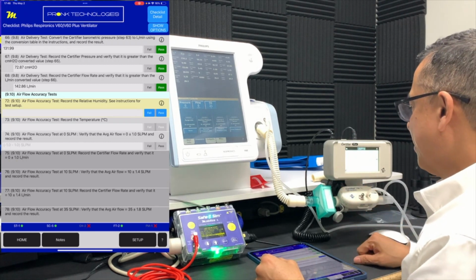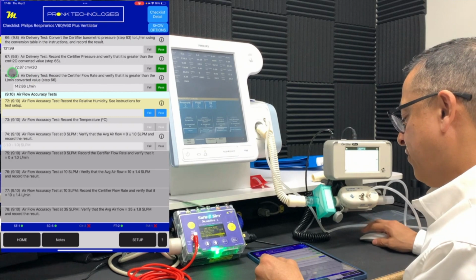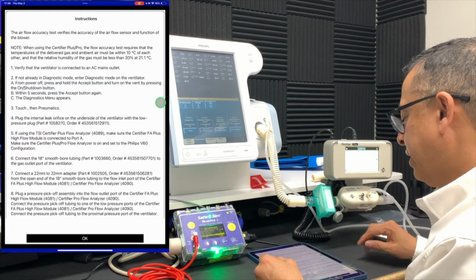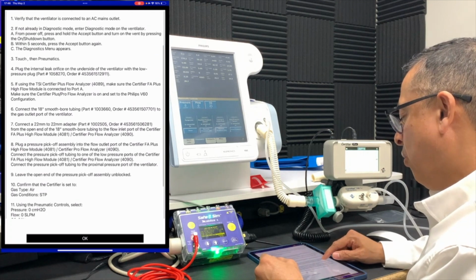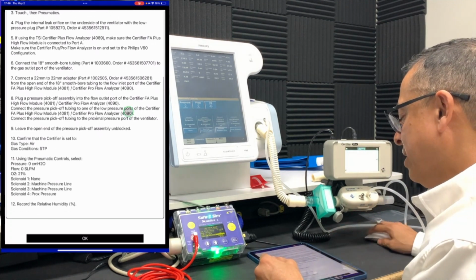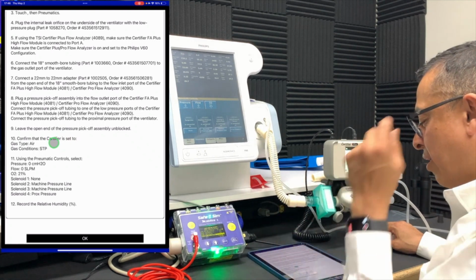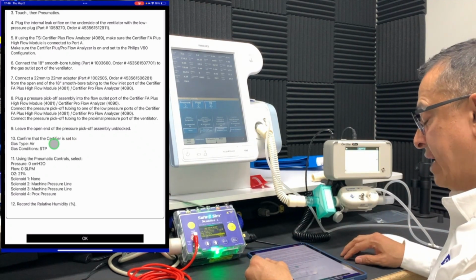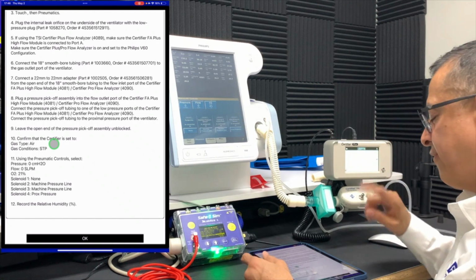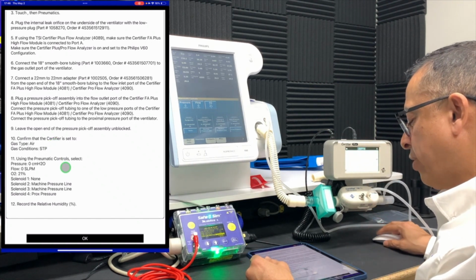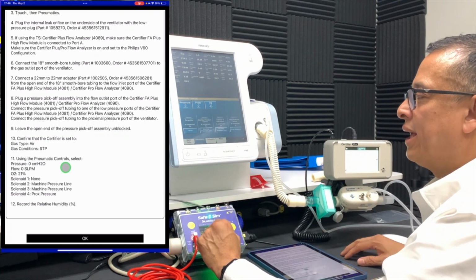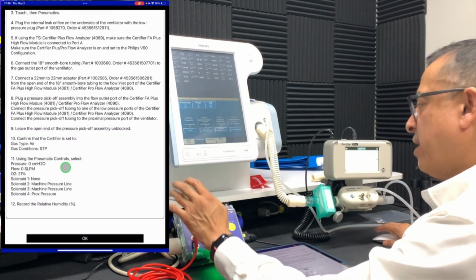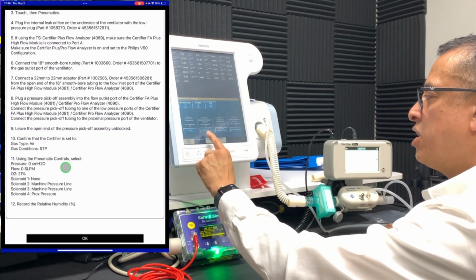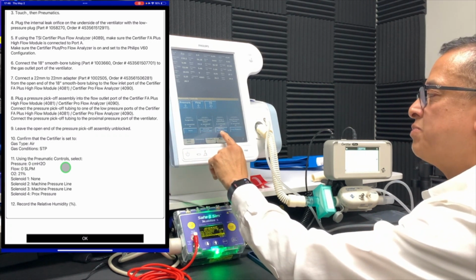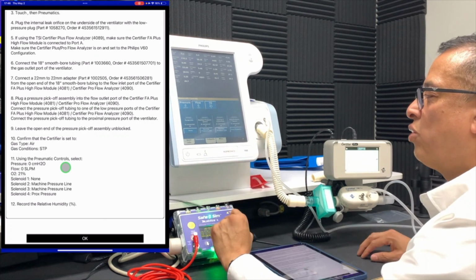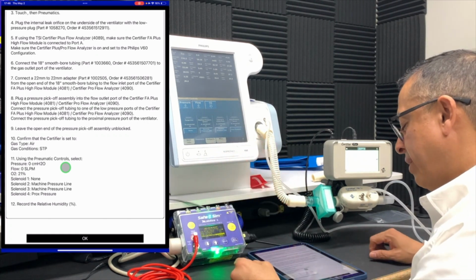So we've set up our Certifier Plus. As always, if you're new to doing the ventilator testing, it's been a while, always good to look at the instructions on how to set things up. You can see here we want to make sure we've set up our certifier to measure air in gas conditions STP, which I made sure to do on my certifier ahead of time. Always make sure that we've set up the ventilator properly as well for our pneumatics. We've checked it before, but always good to check it again. Our solenoid 1 should be set to none, number 2 to machine pressure line, same as solenoid number 3, and the 4th one should be set for proximal pressure to make sure we're measuring that properly.